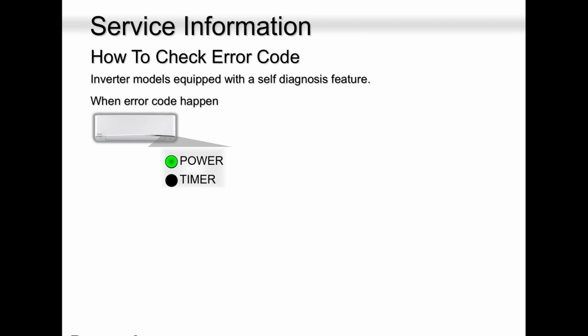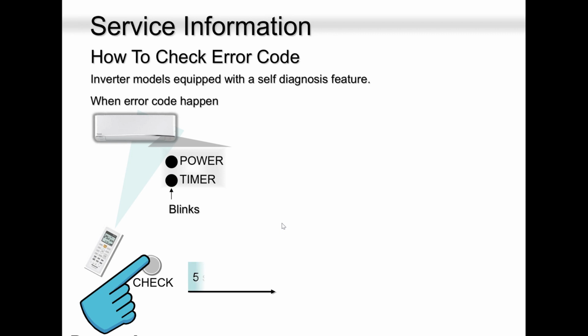In one of my first slides, I mentioned easy retrieving code. Why did I say easy? Because even the homeowner can do it and save you time and money and another trip. If the homeowner calls you and says, hey John, my timer light is flashing, then you can tell John to please do you a favor and retrieve the error code so that you can start somewhere. If the homeowner tells you the green light is flashing, that's not a problem. That means the unit is in defrost cycle or on standby. So please make sure you differentiate between the green light flashing and the yellow timer light flashing. When that light flashes, yes, we have a problem.